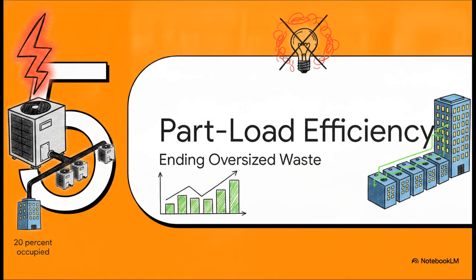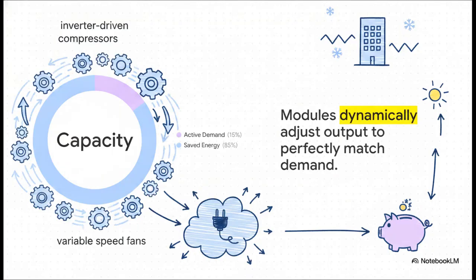Section 5. Mastering part load efficiency, ending the waste of oversized chillers. Historically, buildings relied on these single, massive, oversized chillers. Even if a building was only, say, 20% occupied on a weekend, that giant machine still had to fire up just to meet that tiny load. Talk about a massive waste of energy.